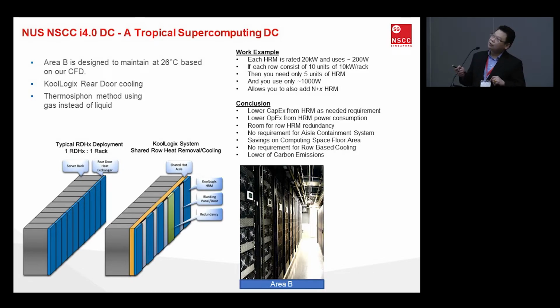However, the KoolLogix system is designed with a shared hot aisle system. What this means is that instead of one rear door cooling one rack, all the rear doors help cool the whole row. So it becomes shared cooling. For example, if one row can take up 200 kilowatts of energy, that is a shared amount. It doesn't mean that each rack has to be 20; it can be 15, then another rack can be 35. Then you just make the appropriate adjustment within the racks. So this gives the advantage of flexibility.